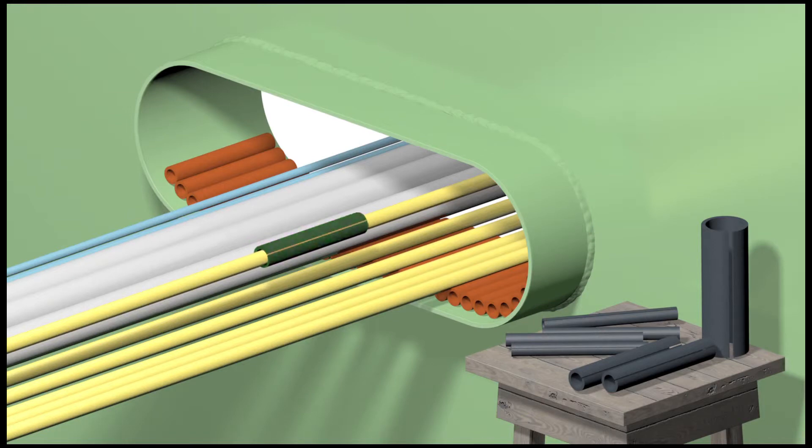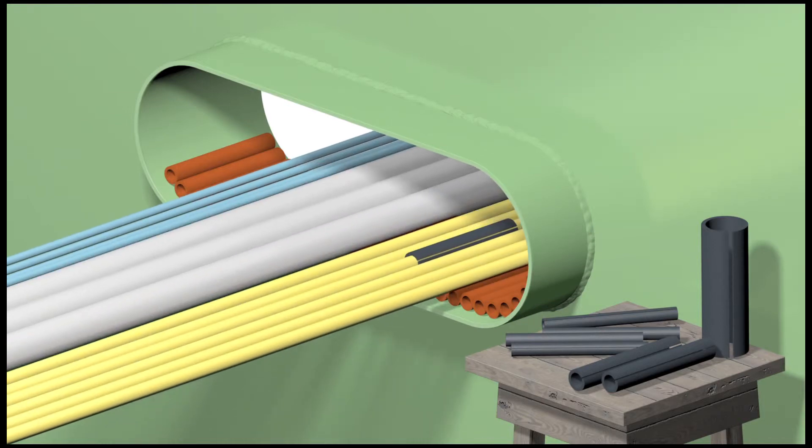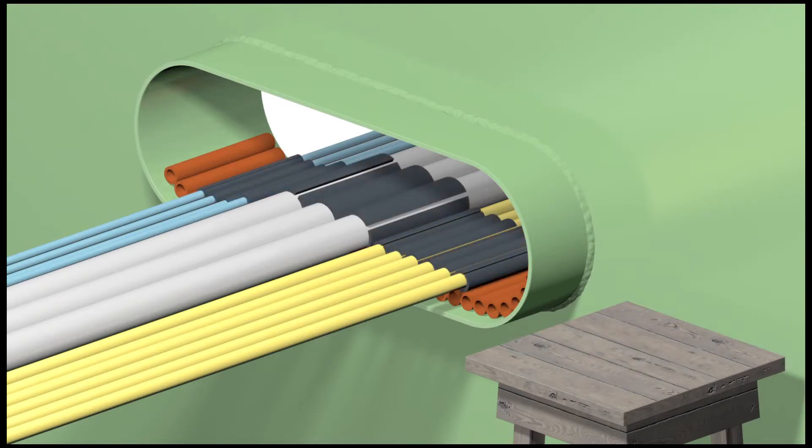A proper fitting insert sleeve is installed around the cables and pushed into the frame. Positioning the insert sleeves in the middle of the frame leaves a free space of 20mm at both sides where the sealant will be applied.